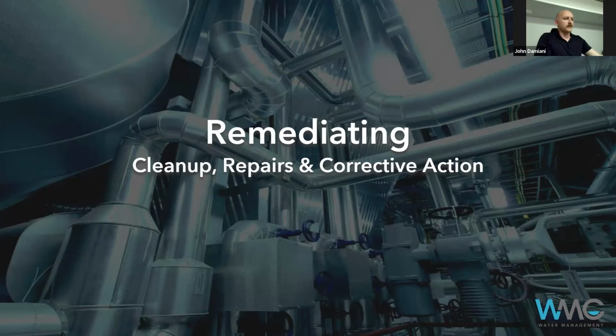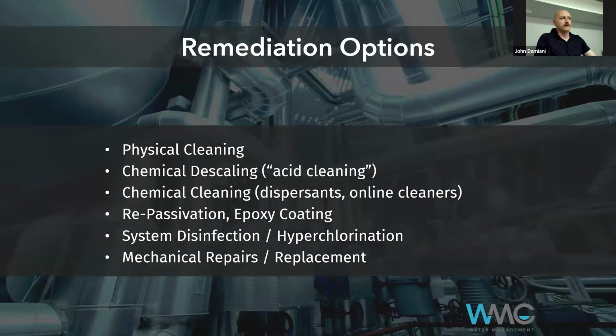So just remediating really quickly, there are lots of remediation options. It's not always the end of the world if you have problems in your system - there are things that can be done to bring it back to normal. This includes physical cleaning; cooling tower maintenance is really important, getting it cleaned seasonally or annually or on whatever your schedule is. Chemical descaling, if you have scale, also known as acid cleaning, can be done. Chemical cleaning with dispersants and online cleaners can also be done.